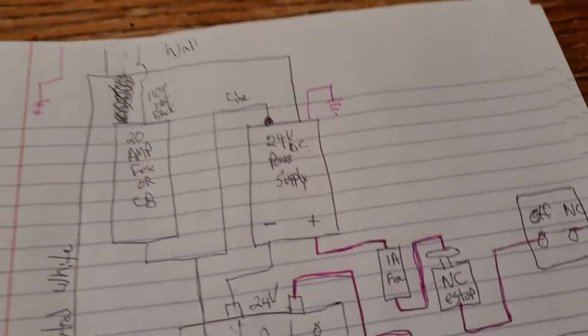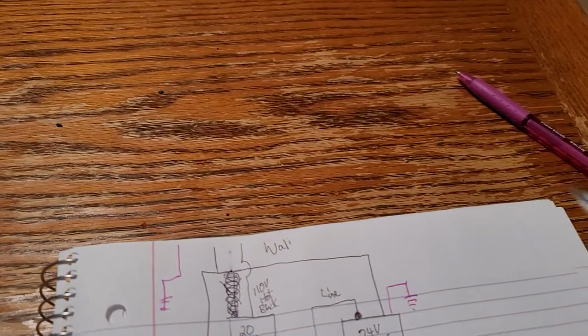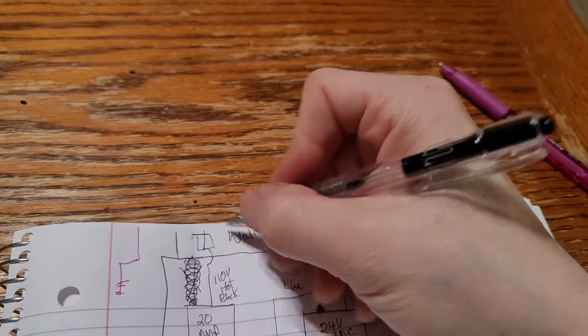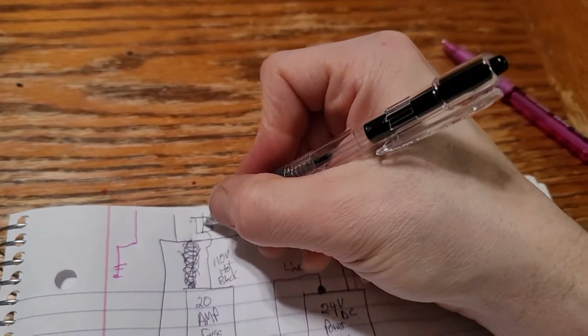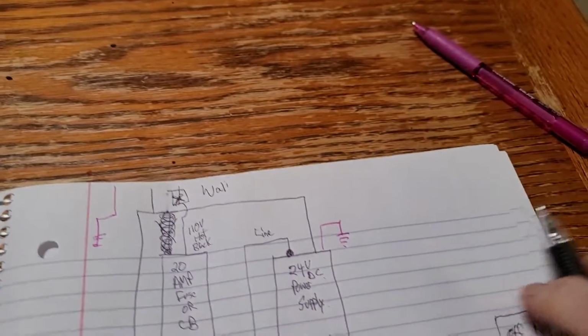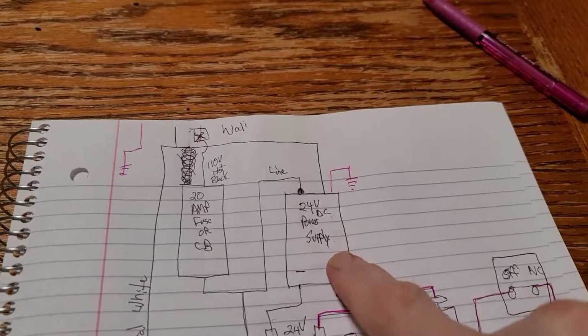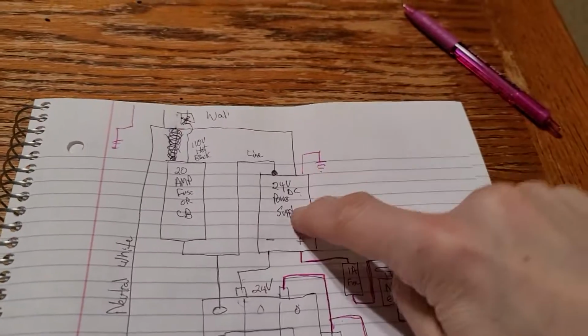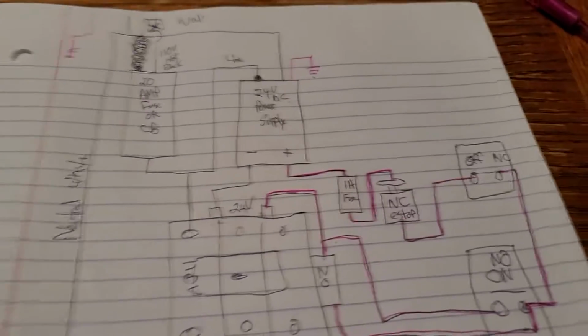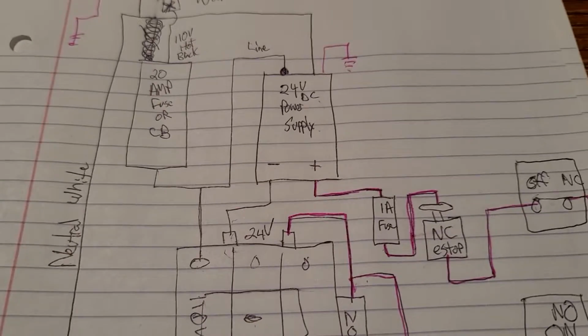And so I asked you earlier if you had a disconnect. A disconnect would disconnect right here. It would disconnect the power coming into the box. If you're going to get one, it goes right here at the very beginning. That disconnect, when it's on, is supplying voltage to this 24 volt power supply. So anytime the disconnect's on, this 24 volts is on. Now that's fine because it's DC and it's low amperage and it's not going to hurt you.